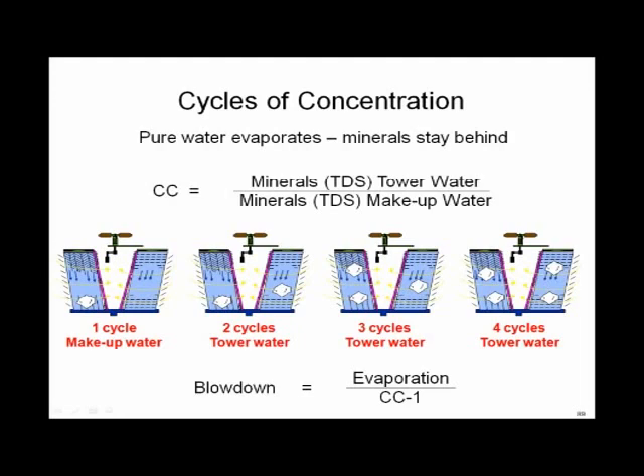Well, I get my cooling tower going on the left-hand side. I've got all this water in there. Let's just take all these solids, just make it one big rock, okay? So we've got 1 cycle of concentration when we start off. We've got 1,000 gallons of water in that tower. We evaporate that water down, we've got 1 rock. Okay, great, that's good. But when we evaporate that 1,000 gallons of water down to 1 rock, what are we going to do with our cooling tower? We're going to make up another 1,000 gallons of water. And when that other 1,000 gallons of water comes in, it brings another rock.